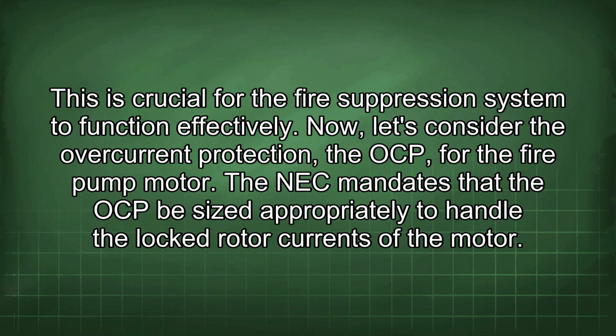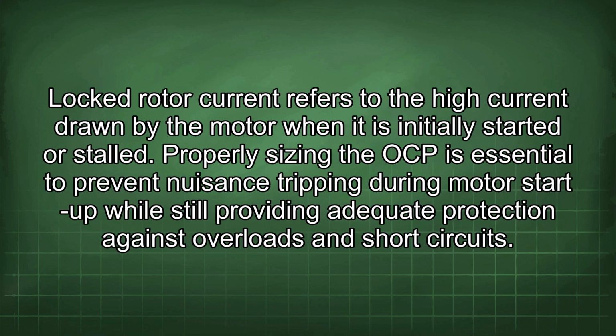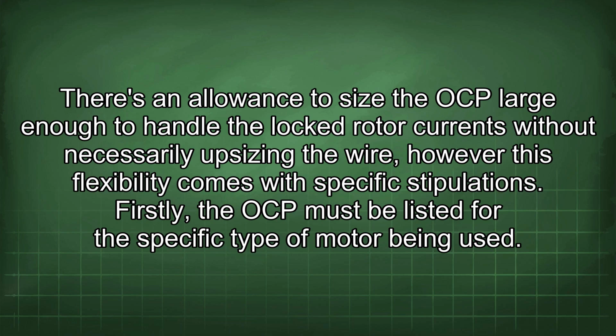Now let's consider the overcurrent protection, the OCP, for the fire pump motor. The NEC mandates that the OCP be sized appropriately to handle the locked rotor currents of the motor. Locked rotor current refers to the high current drawn by the motor when it is initially started or stalled. Properly sizing the OCP is essential to prevent nuisance tripping during motor start-up while still providing adequate protection against overloads and short circuits. There's an allowance to size the OCP large enough to handle the locked rotor currents without necessarily upsizing the wire. However, this flexibility comes with specific stipulations.